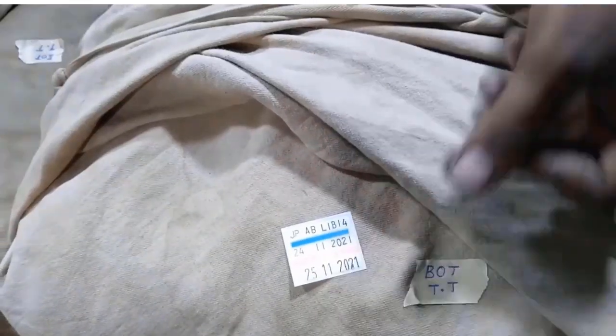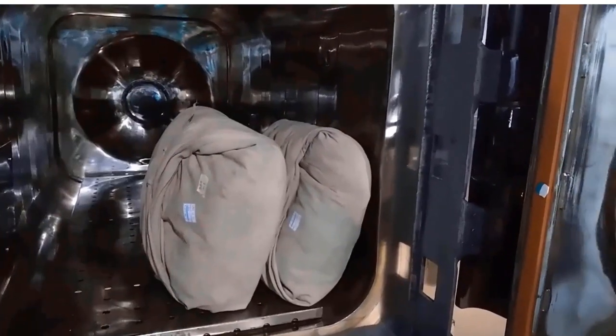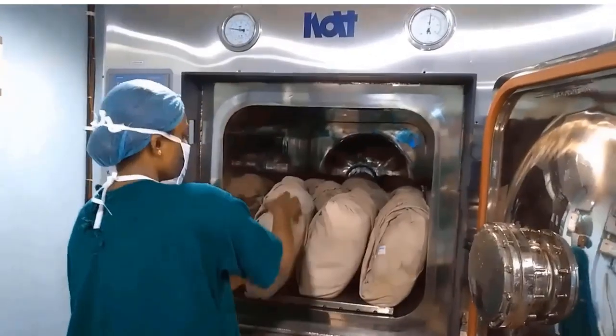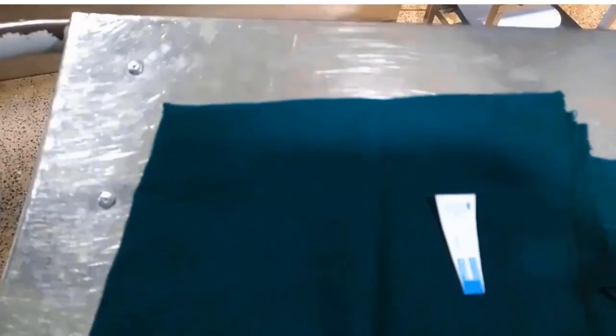Keep a minimum of linen bundles only in the autoclave machine with class 1 and class 5 indicators. Don't mix instruments bins and bundles, to avoid overload of steam penetration.